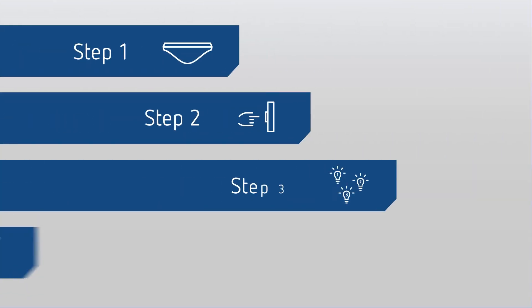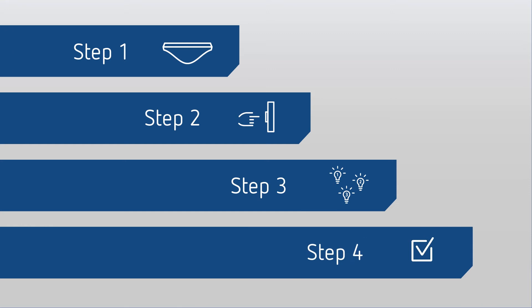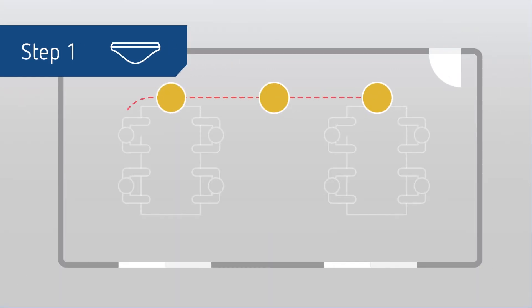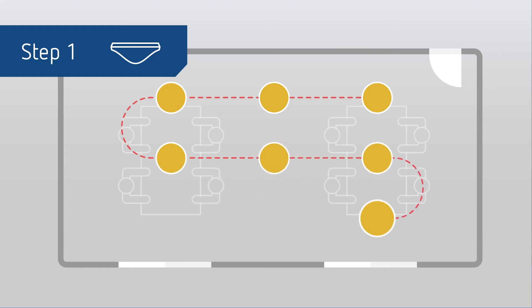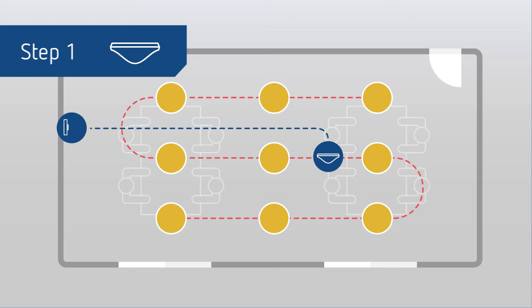Installation of the lighting system is completed in four easy steps. After power-up, T-Ronda DALI automatically identifies all connected DALI lamps, assigns short addresses and manages them in a list. The detector waits for configuration and indicates this using an LED flashing pattern.